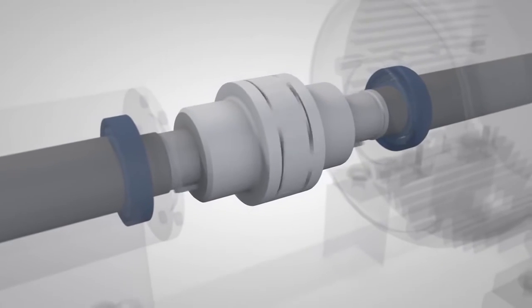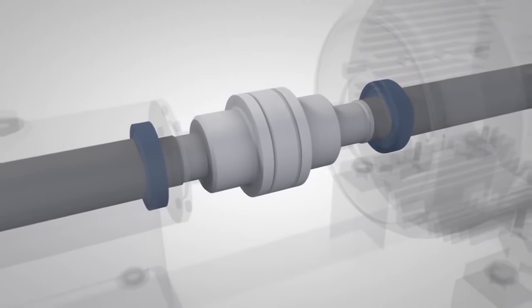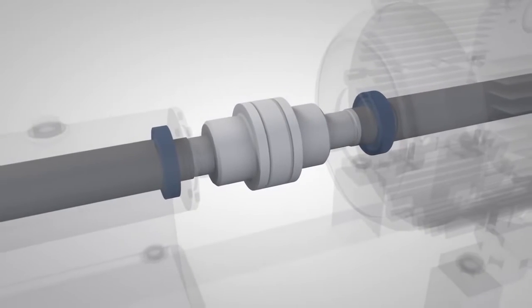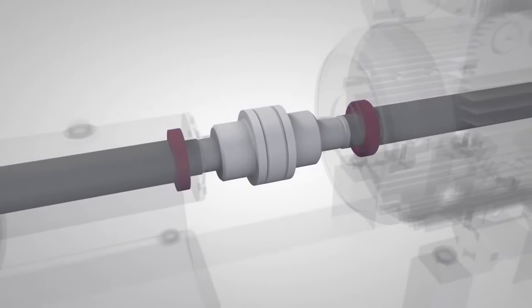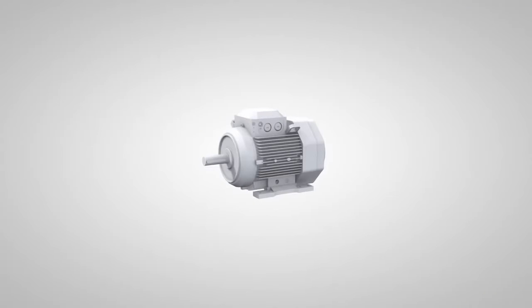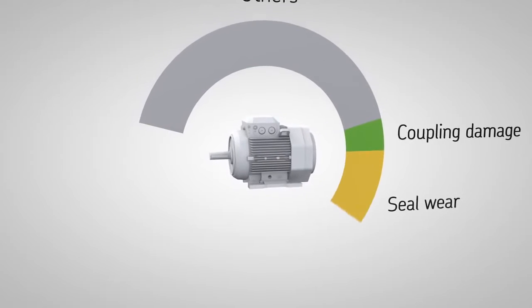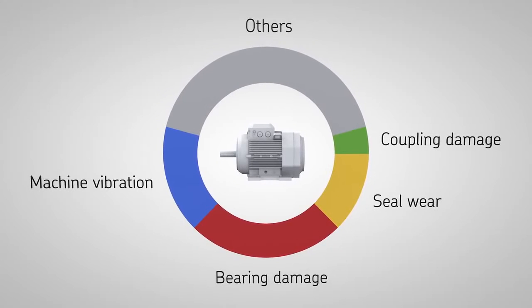Even flexible couplings that are designed to withstand minor misalignments cannot prevent negative effects on other machine components. Field experience shows that around 50% of machine breakdowns can be attributed to damage resulting from shaft misalignment.